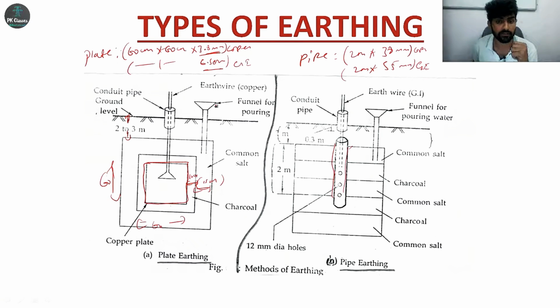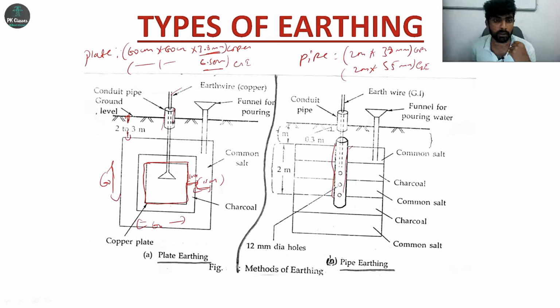And next there is a funnel for pouring the water in the summer season, because if suppose water enters into the earth chamber, what happens, salt will be there, charcoal will be there. So salt water is a good conductor of heat and electricity, already we know, right? So that's why the funnel is for pouring the water in the summer season. Next there is earth wire for external connection for the electrical appliances or electrical equipment. This is conduit pipe for the passage of earth wire, right? Earth resistance must be less than 5 ohm based on IEC standard.